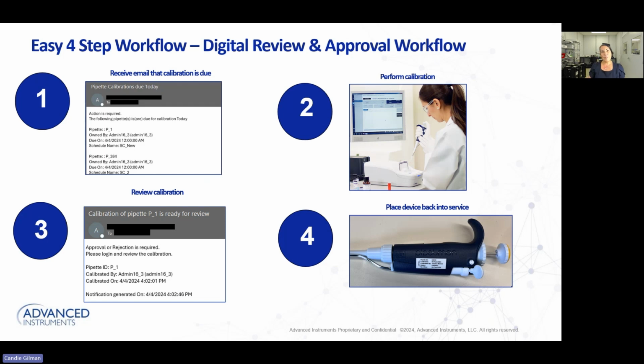And then at that point, step number 2, the pipette's brought to the calibration lab, the calibration is performed. Step number 3, the person that's responsible for reviewing the calibration data receives an automated email from the system and reviews the data. And then once that data is reviewed and it's passing and approved, step number 4 happens. The system can generate a calibration sticker. You apply it to the pipette. You place that device back in service. So really, really easy workflow, and it's meant to be digital. So if you want to be completely paperless, our system can help you achieve that.